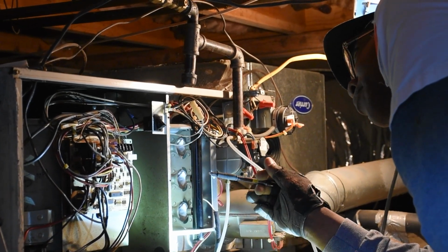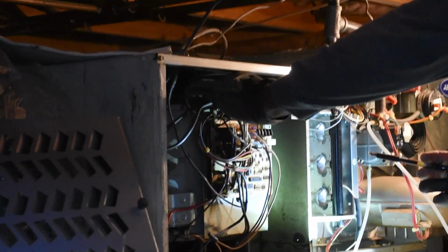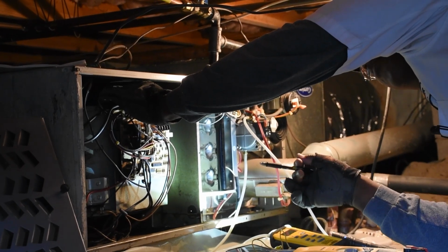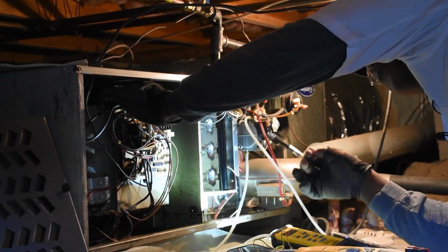Once you have full flame, the burners are going, we have what is called a temperature control switch that's attached to the blower motor. And it's attached to the heat exchanger. Once the heat exchanger heats up to a certain point and it knows, okay, I'm hot enough, it sends a signal for the blower motor to start operating. And the blower motor starts and starts pushing the heat off the heat exchanger into the home. And that pretty much completes the heat cycle.